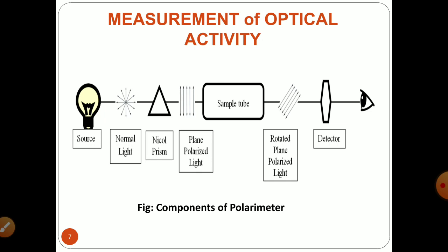The light source commonly used in a polarimeter is a sodium vapor lamp. An optical prism or polaroid lens is used as the polarizer, which converts the ordinary beam of light into plane polarized light. The optically active substance under observation is kept in the sample tube. The analyzer or detector is used for making a half-dark and half-bright circle during the measurement of optical rotation. It can be rotated and is connected to a scale which helps in reading the angle of rotation.